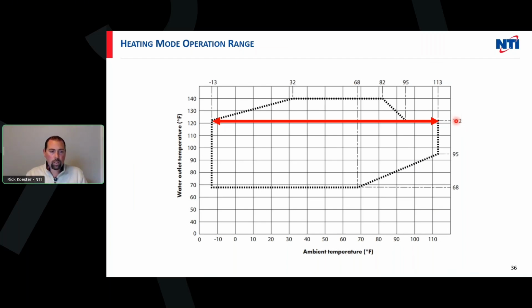From 122 degrees to 95, I'm going to get a consistent water temp throughout the entire operation range here from -13 all the way up, right? So if I were designing a system and my emitter needed 130 degrees, I can tell here that once I get to about 8 degrees Fahrenheit, I know that I'm going to start to tail off. I'm not going to be able to provide 130 degrees of water below that.